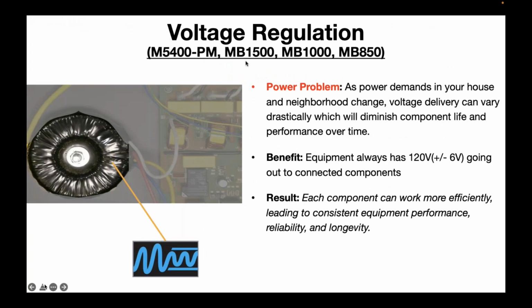Voltage regulation is a more expensive feature, only found on some higher-end products. It keeps the equipment plus or minus 6 volts from 120, so if it gets above 126 or below 114, it won't shut down - it will adjust, adding or subtracting voltage to keep it at 120 volts. If it goes beyond that 6 volt range in an extreme way, automatic voltage regulation will shut the unit down to protect what's connected. Voltage regulation is a great way to protect equipment and the power supply from gradual damage, so everything works more efficiently and at its best performance.